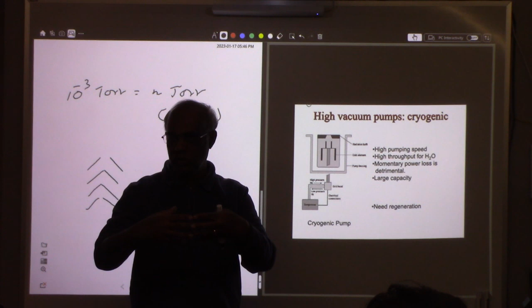So this momentary power loss is very detrimental. You can have very large volumes to pump, but regeneration means once you finish pumping, you have to isolate the system, you cannot just expose it to air since it's already too cold. So you isolate the system, then open your vacuum. Next time you use it, you have to make sure you remove all the gas. Most of the time when you heat it to room temperature, the gas can dissolve away, but that's not necessarily true, some molecules can still stick onto the surface even at room temperature. That's why you need to heat it a bit and regenerate.